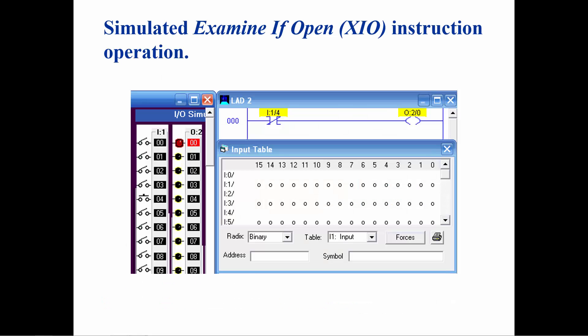When the switch is closed, a 1 is placed in the input table. The examine if open will interpret this condition as false and not allow rung continuity, just like a normally closed relay contact will not allow current flow when the relay coil is energized. The address of the contact does not turn yellow, indicating that there is no logic continuity.